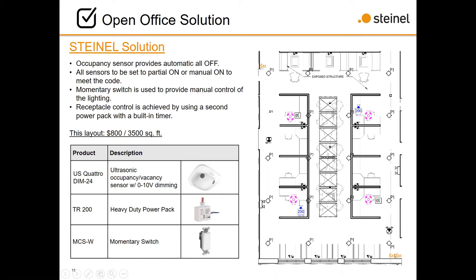You've got override on 2 different zones with the momentary contact switch: press and hold, it'll dim up. Press and hold again, it'll dim down. So you're providing manual override as well. And you've got receptacle control. One of the power packs is powering the 4 sensors. The other power pack is controlling the receptacle circuit. So we're providing receptacle control here.